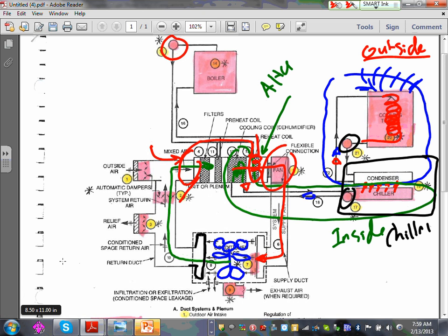And they use compressors. They compress that refrigerant, my friend. By compressing the refrigerant, it increases the pressure and the temperature, and then it reduces the temperature of the refrigerant. When you reduce the temperature of the refrigerant right next to the water, it picks up the heat from the water. That's how we get it in. And all the heat coming from the room through this coil will be picked up through the condenser, taken out to the cooling tower, shot up in the air, and come back.